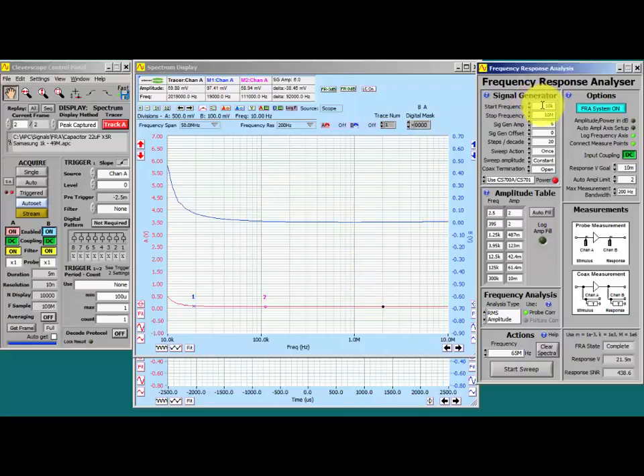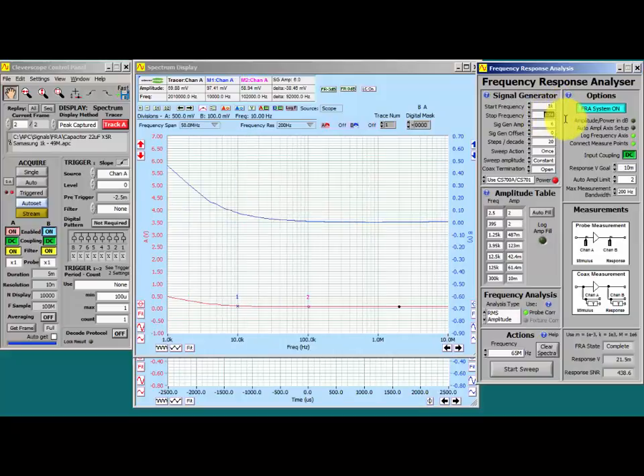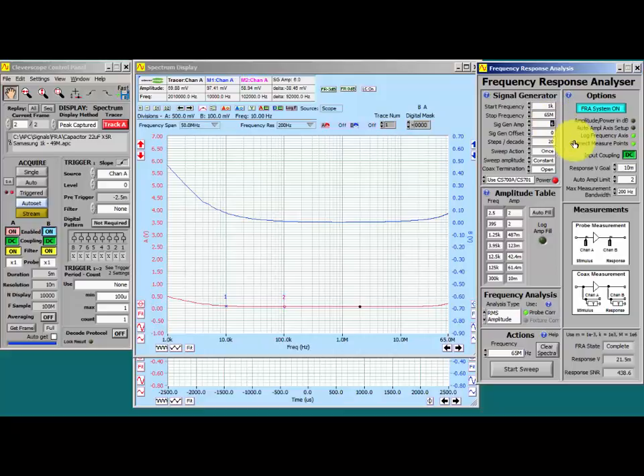So up here we'll set the test frequency to 1 kHz and we'll go up to 65 MHz. We'll go with a signal generator amplitude of 6 volts and this is using the CS701. We go for as high a voltage as we can manage.